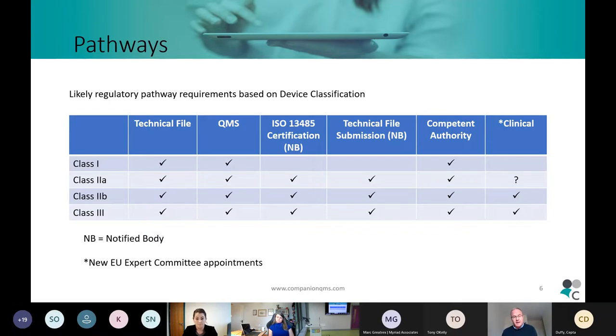At the other end of the scale, in the bottom row, a class three device, the requirements are much more extensive. The technical file, while on the outside may look similar, requires a significantly greater level of detail than for a lower class of device. Similarly for a quality management system, while the overall framework might be similar, the actual internal requirements and controls in a risk-based approach will be much more extensive.